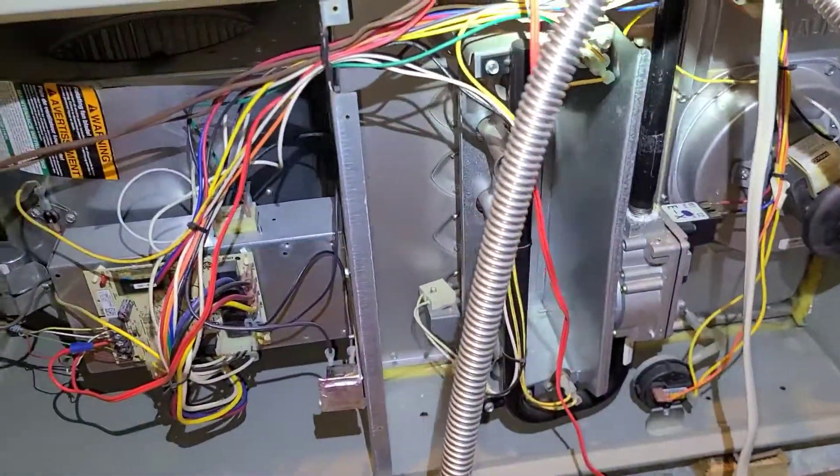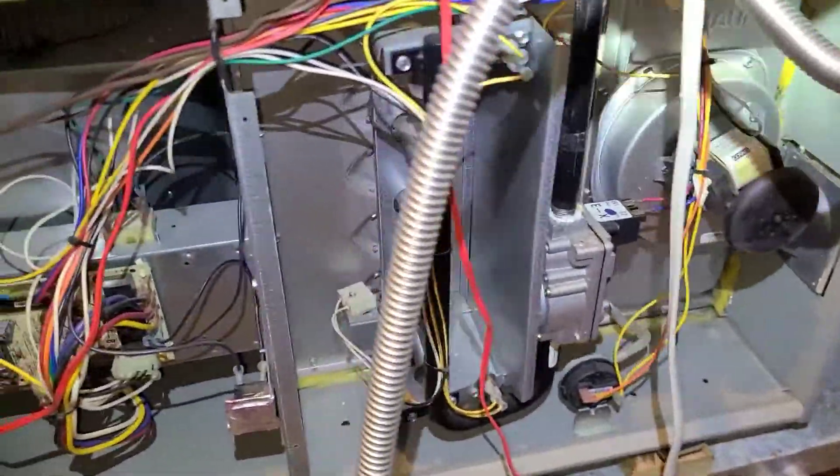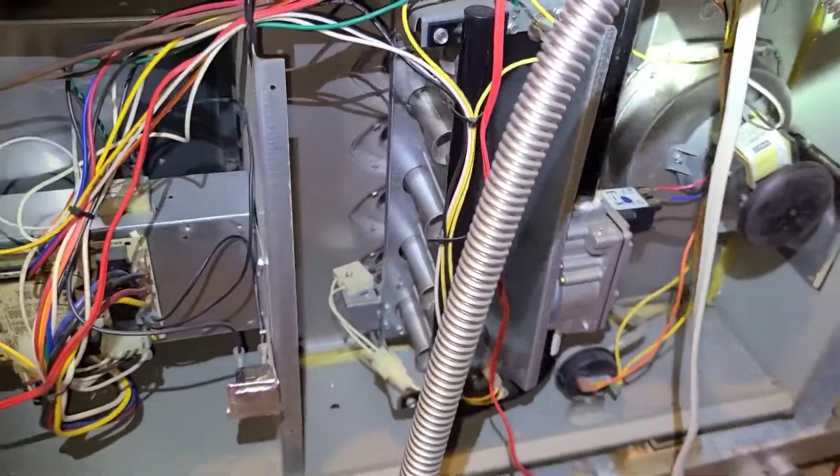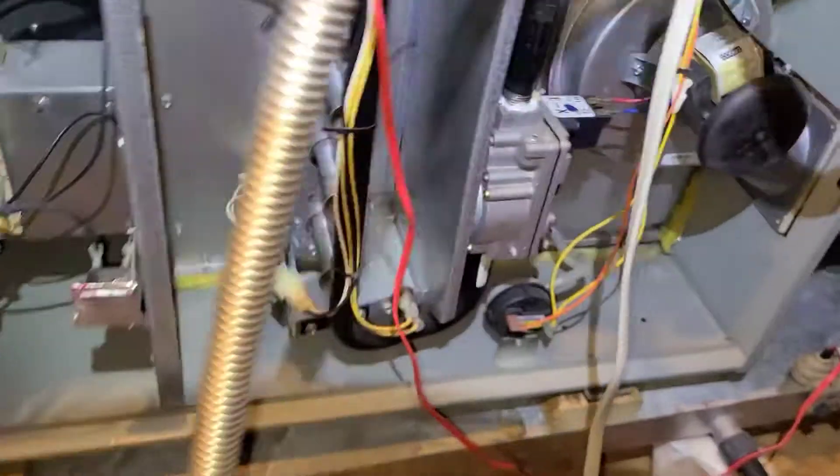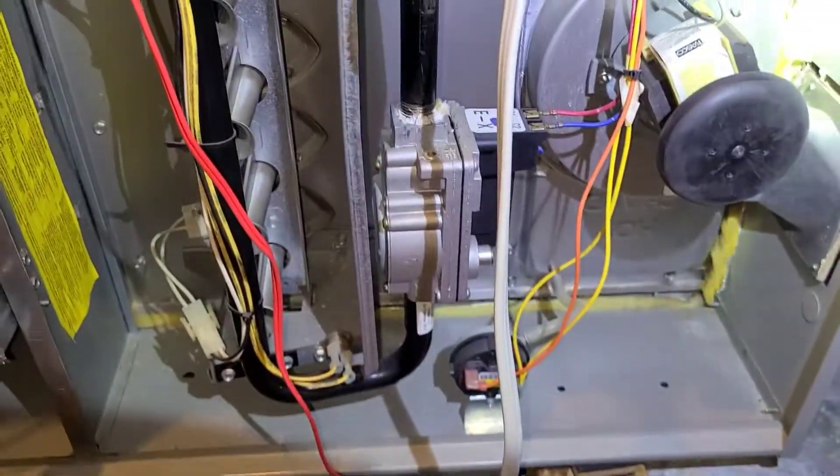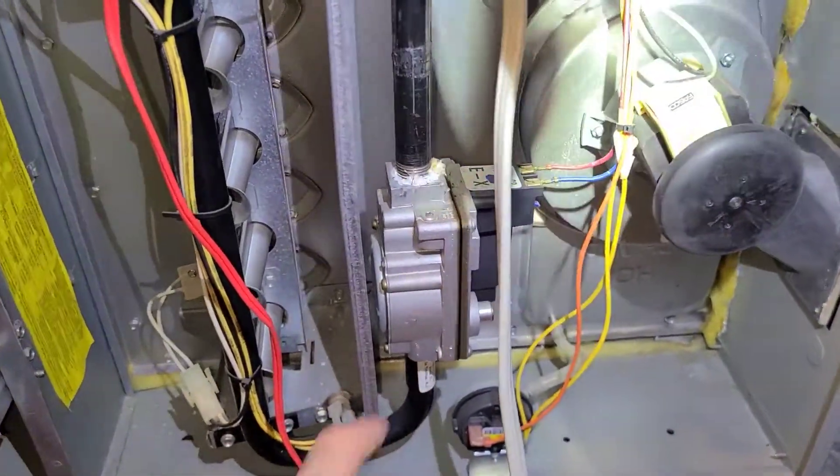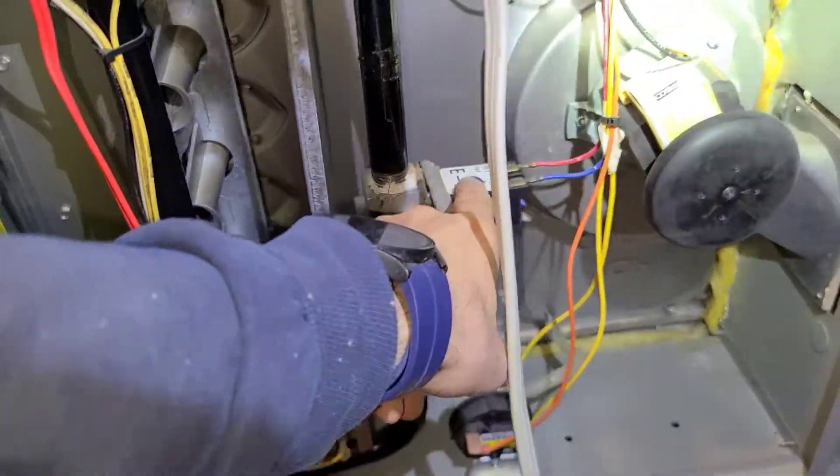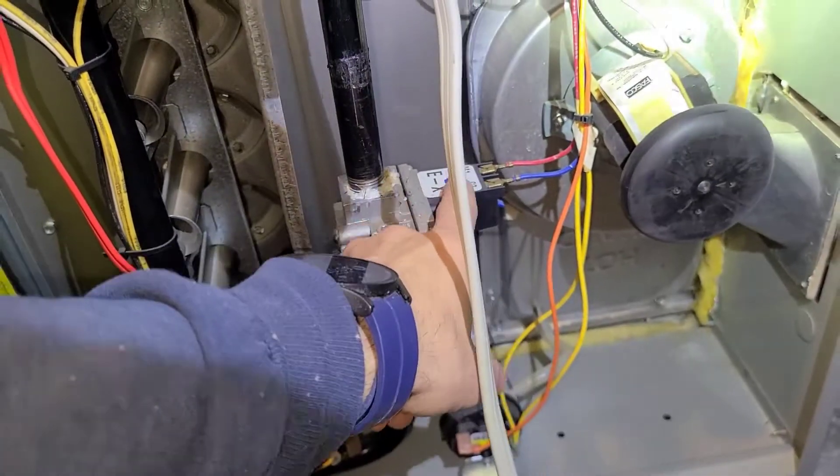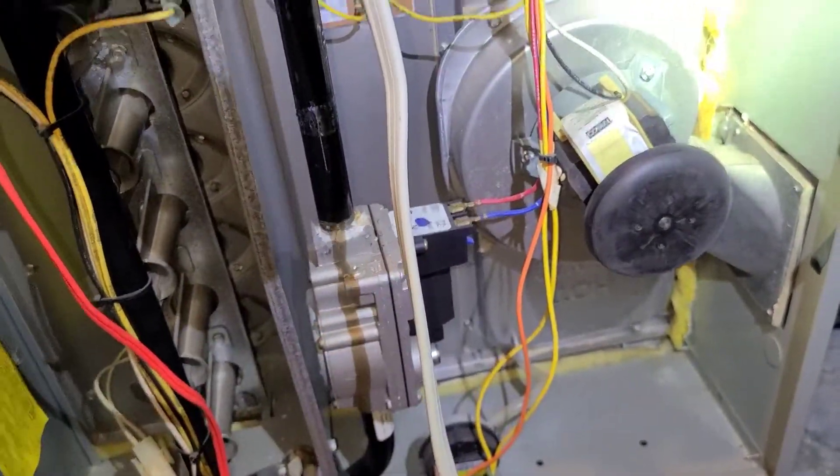Got a Trane furnace right here. This is a unit that I pre-diagnosed. The unit would not heat because the control board was not sending 24 volts to energize the gas valve.